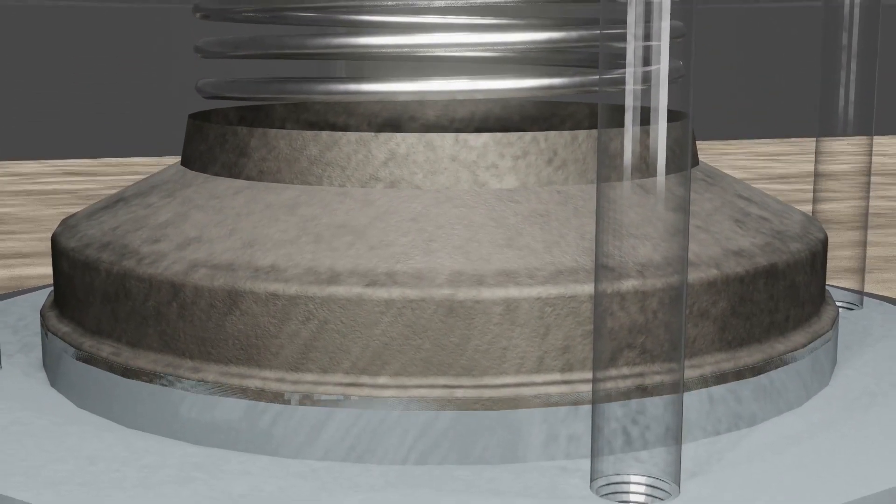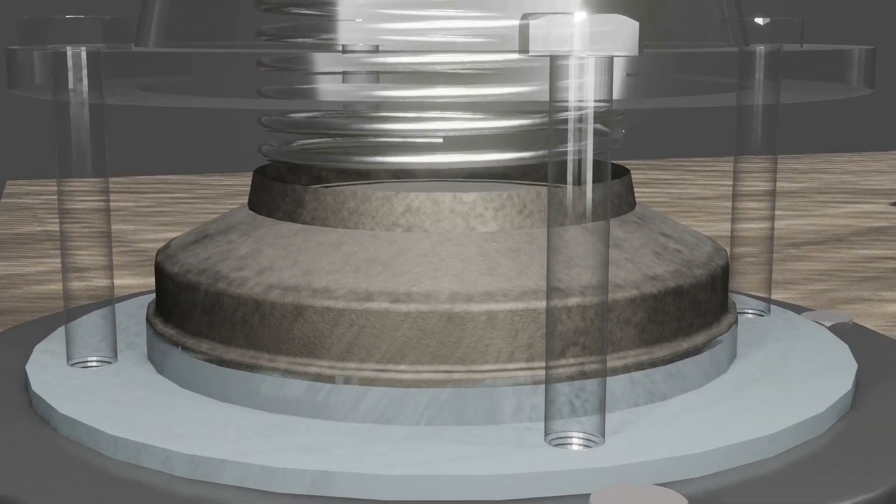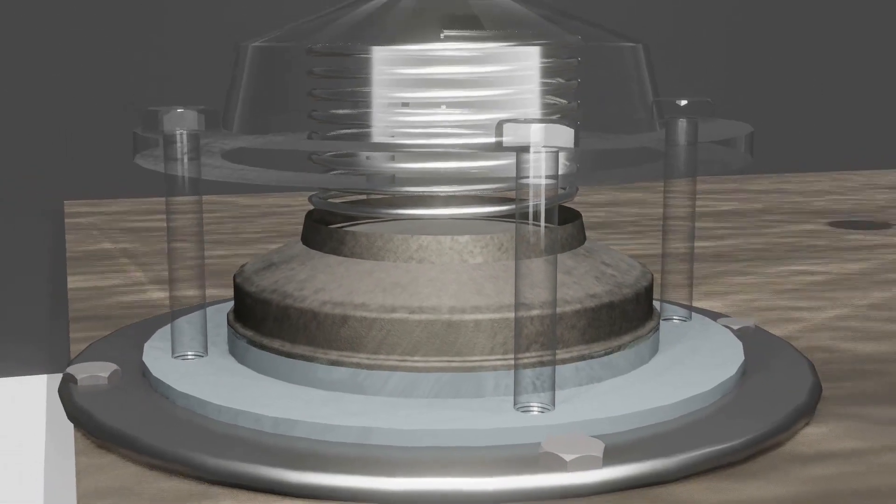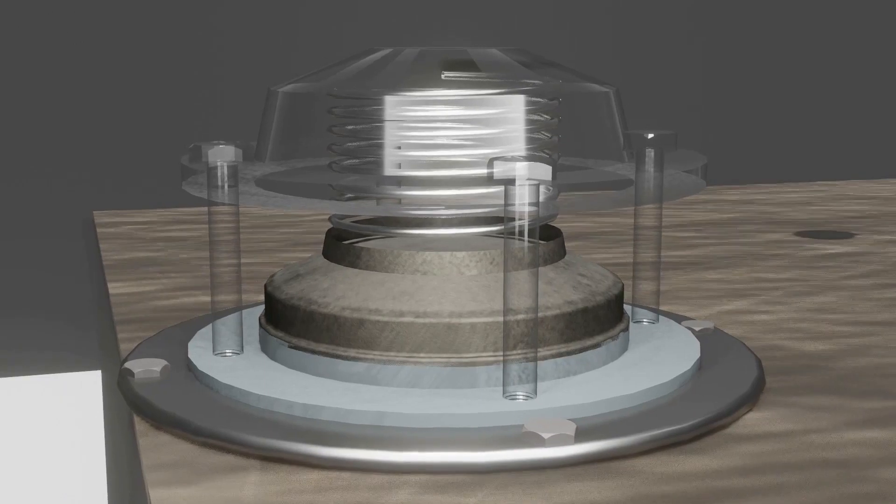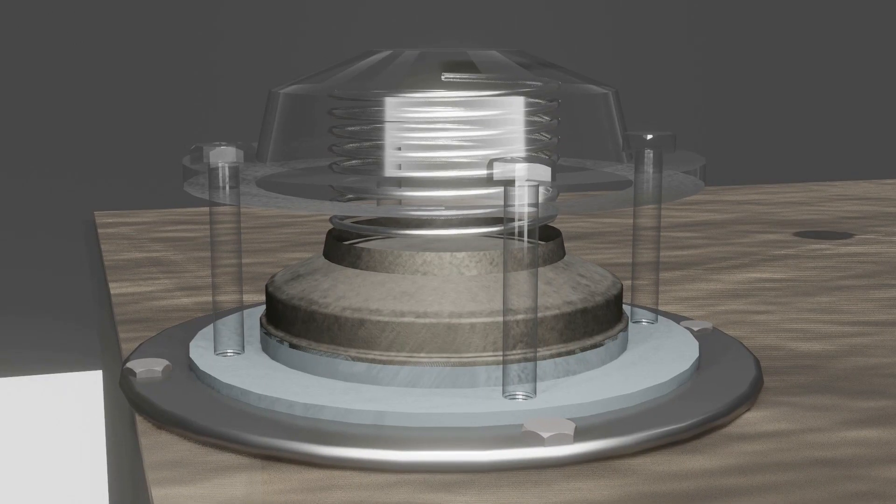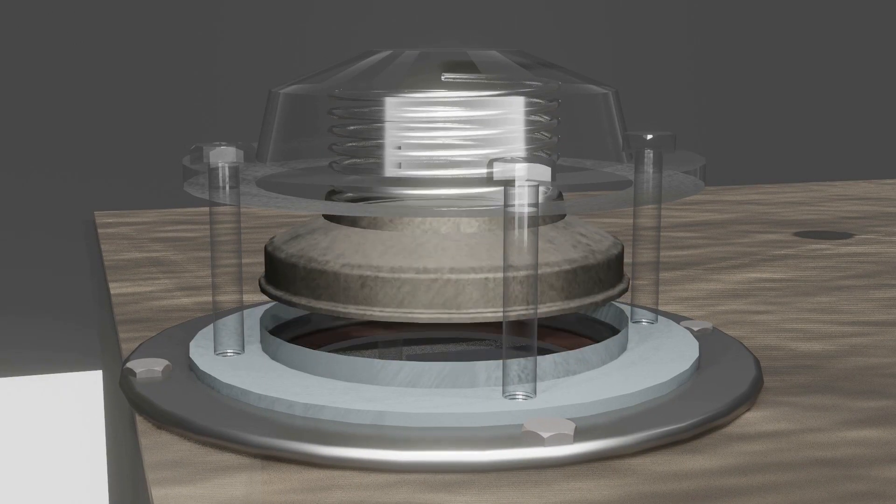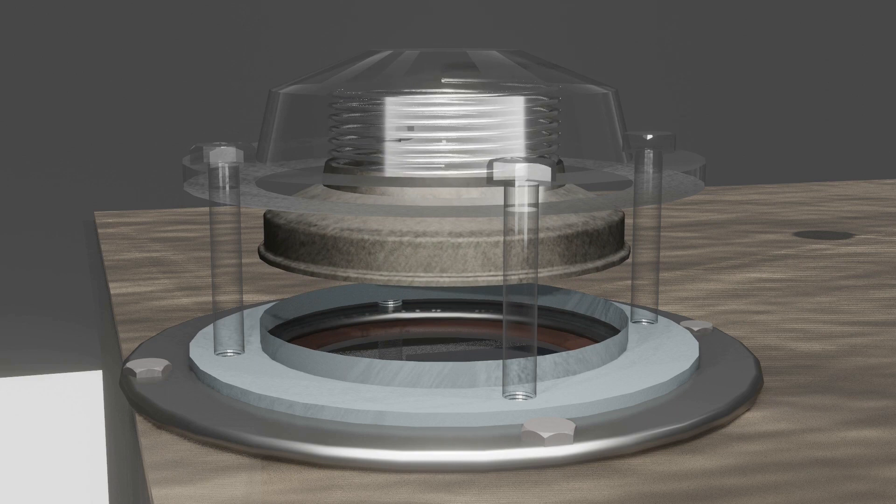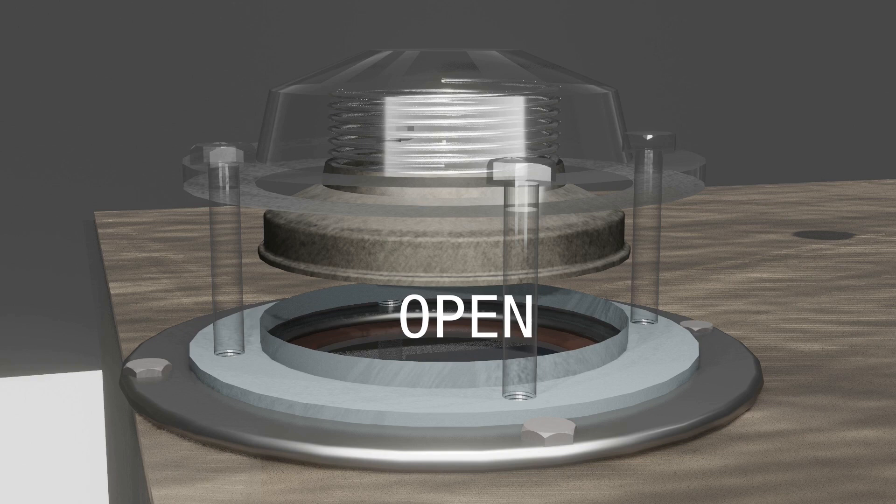But if a fault occurs inside the tank and pressure got built up inside, then whenever the amount of pressure inside the tank is greater than this spring pressure, disc moved upside and the spring went to compress as you see here. And due to that flange and disc apart and the valve got open. Hence all pressurized energy get out from the tank. And it will prevent the tank from rupture.